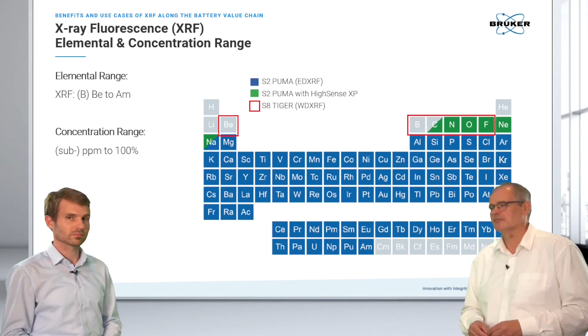So maybe Kai, you can tell us a bit more about what type of samples we can analyze in XRF, and maybe also a few words on sample preparation. Now I want to solve the riddle from the beginning. The big advantage of XRF, I said, is that we are using an effect in the atom shell which uses inner shell electrons. And therefore we are independent with XRF of the chemical binding and also the state. So we can analyze loose powders or liquids. These can be filled into liquid cups, which are shown here, and analyzed directly.